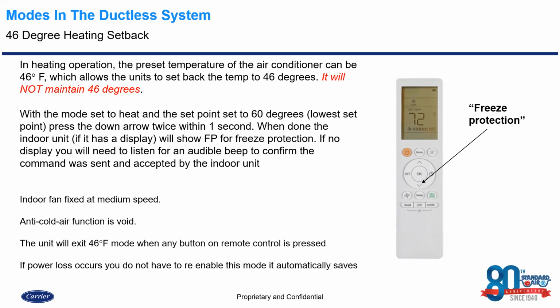Okay. And a nice unique feature, if power loss does occur, you don't have to worry about re-enabling this mode as it automatically saves. So if you have a power outage and the power comes on an hour and a half later, the system finally comes back on, this is still going to be in freeze protection. Now, I have tested these up for about 3 hours that it stayed in freeze protection. After 3 hours, it was about 3 hours and 15 minutes, the system did reset itself and it actually had to be manually re-enabled. So it depends on the severity of the power outage and how long it's out for that it will maintain that mode. But I can say roughly for sure, at least 2 hours.